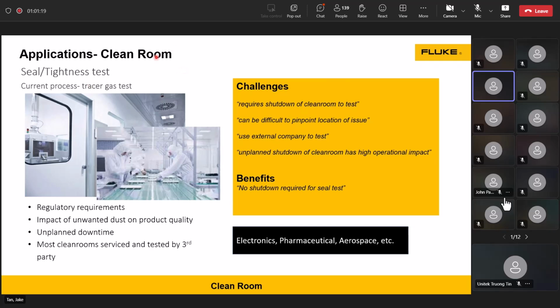For the clean room side, usually the clean room door, even the window, are airtight seals. They have to contain - once you shut the door, for example, the pressure from inside the clean room and the external, for example the corridor, have to maintain a pressure gradient difference. Otherwise the contaminants might flow in.